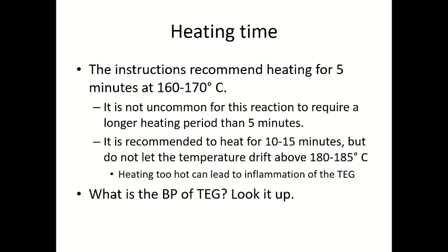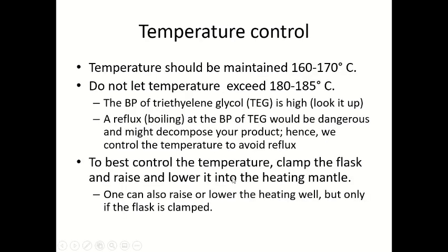Then, this brings up a question that you need to look into beforehand, because you need to know the boiling point of the TEG. You have to look for it. That's why the temperature control is so important, right?